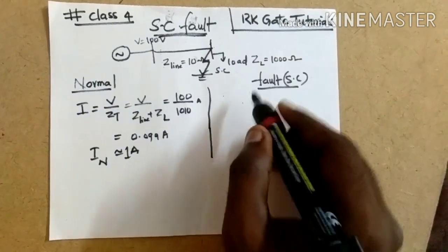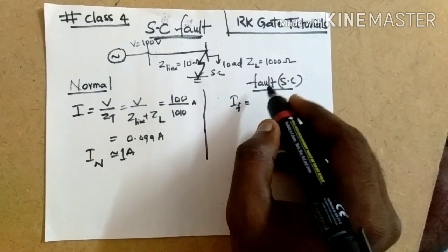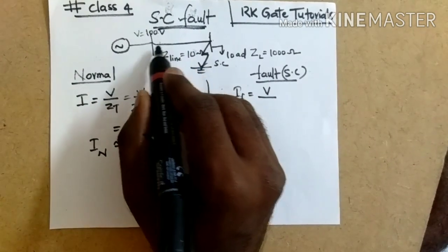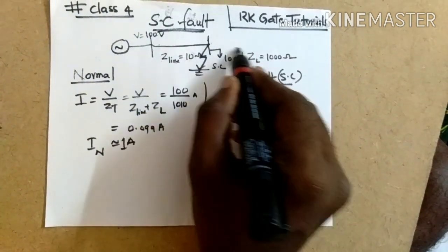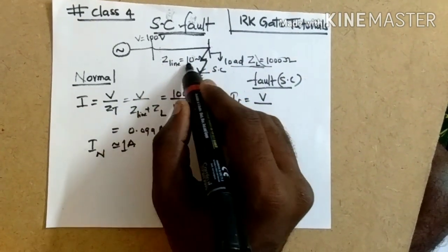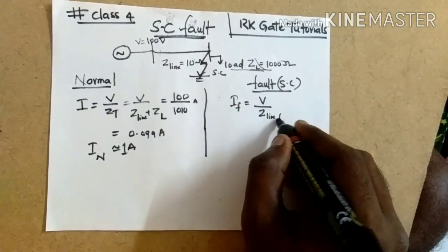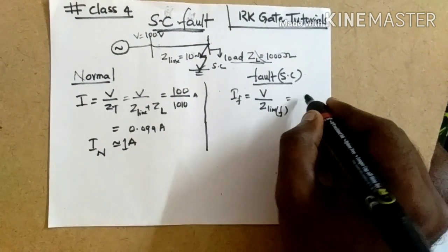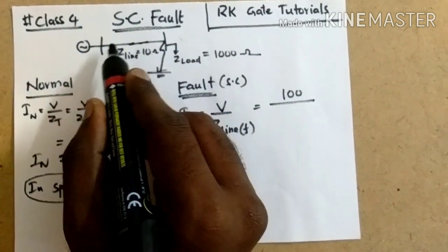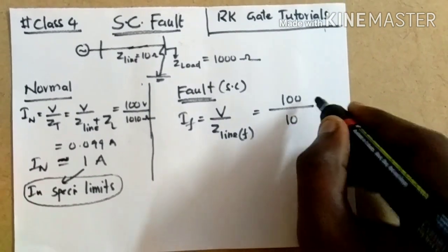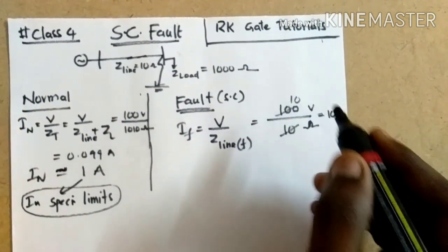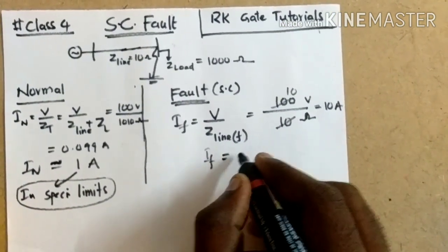Now let us go to the fault condition. The fault current I_F equals voltage divided by the fault impedance. When the fault takes place at this point, we cannot consider the load impedance because current is not going to the load. We only consider the line impedance as the fault impedance. So fault impedance equals Z_line equals 10 ohms. The fault current is 100 divided by 10, which equals 10 amps.